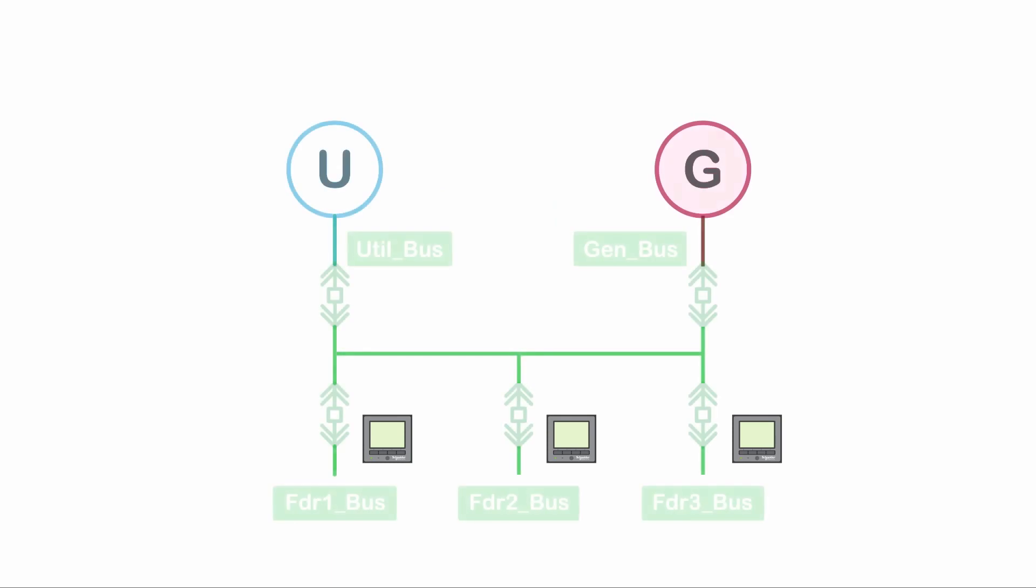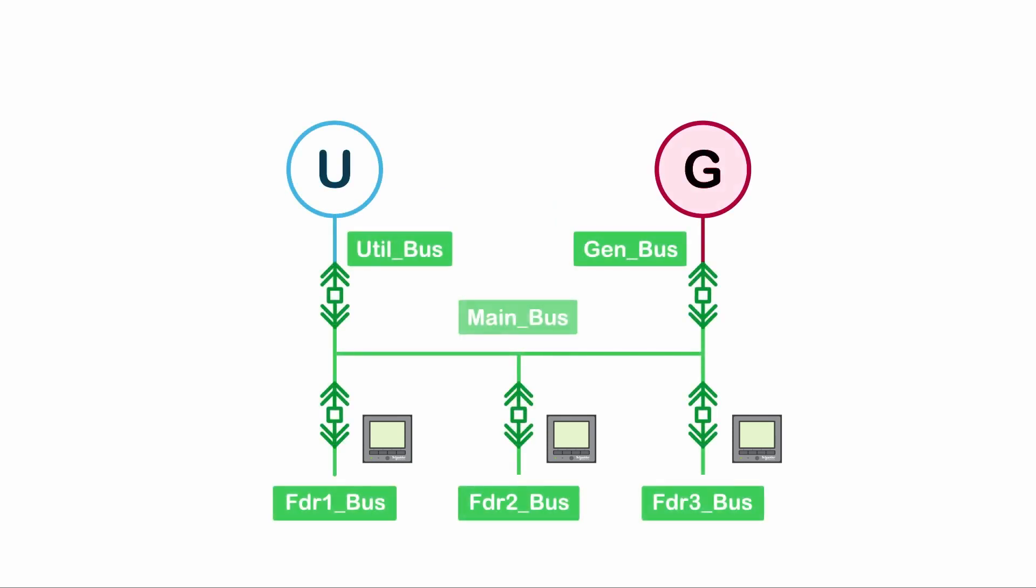Finally, there are meter components. These function in the same way as sources, but at a lower priority. That is, if the sources and breakers indicate a bus should be de-energized, but a meter is still reading voltage, we apply a special color called unknown to tell the user that the engine cannot determine what source is energizing the bus.